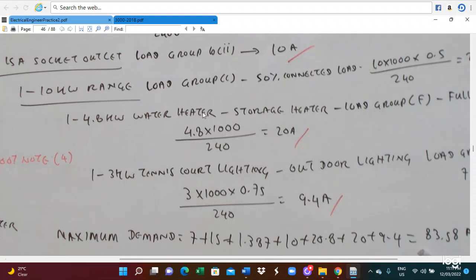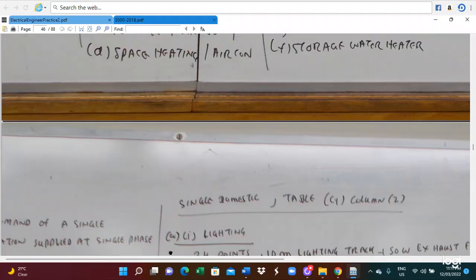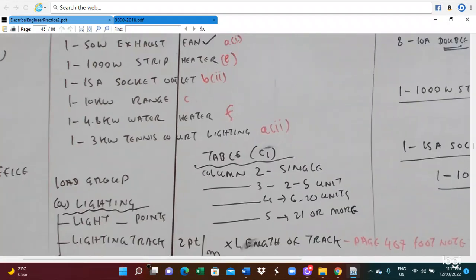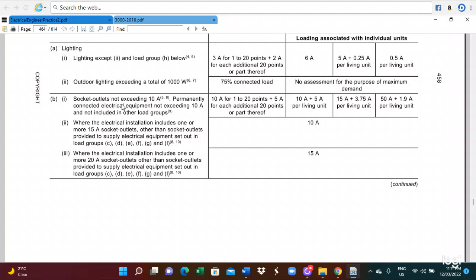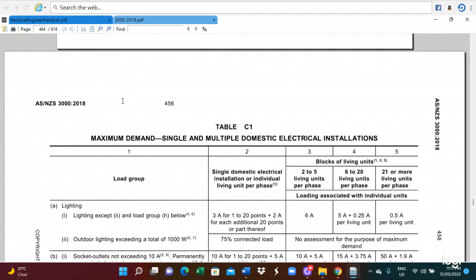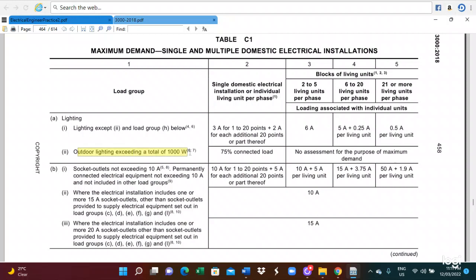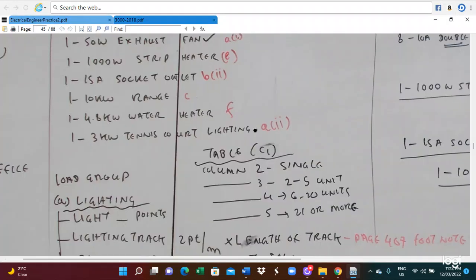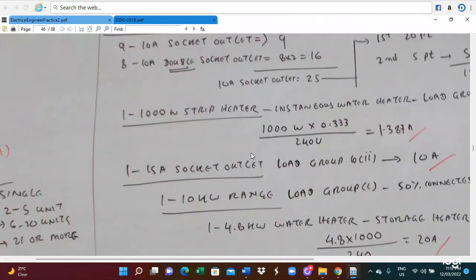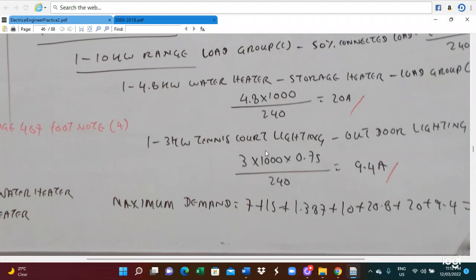And finally, it is also given the 3 kilowatt tennis court lighting. The 3 kilowatt tennis court lighting is a load group A2, because load group A2 is here. This is the outdoor lighting. Outdoor lighting exceeding 1000 watts. So in this case, we have to take the 75% of the connected load. So 75% of connected load, load group A2, for this standard scope lighting. So that will be 3 multiplied by 1000, multiplied by 0.75. So you get the power, divided by 240 volt, you get 9.4 ampere.